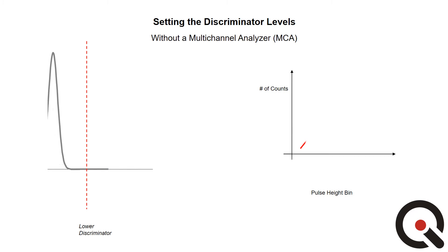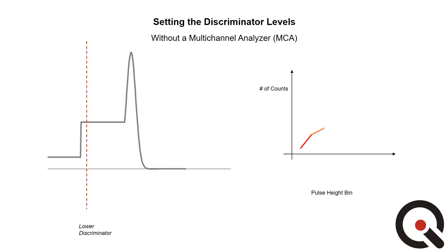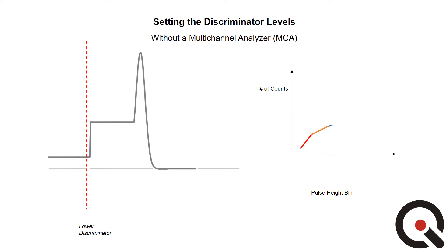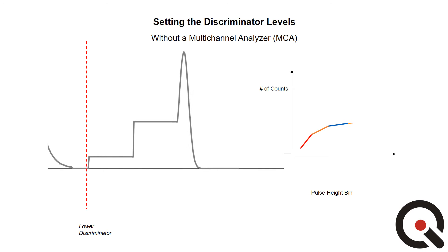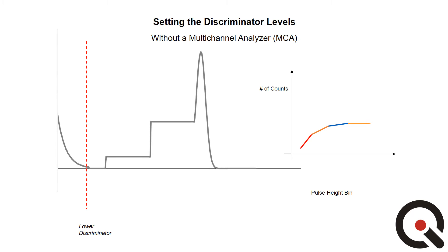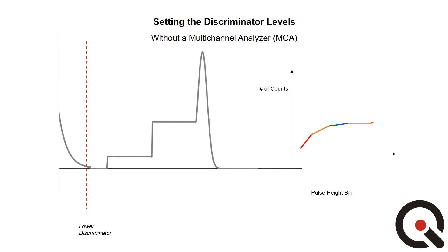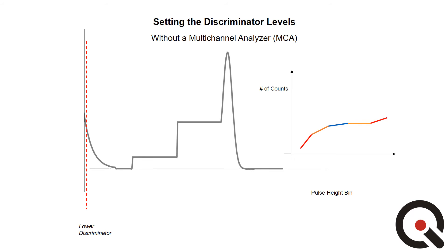Without a multi-channel analyzer, the underlying pulse-height spectrum is not visible and must be inferred from the way in which the neutron counts per unit time change with the discriminator settings. As the lower discriminator setting is moved to the left, the counts per unit time generally increase, except for the valley region, in which it remains constant. These graphs do not always allow one to clearly locate spectrum features such as peaks and valleys.